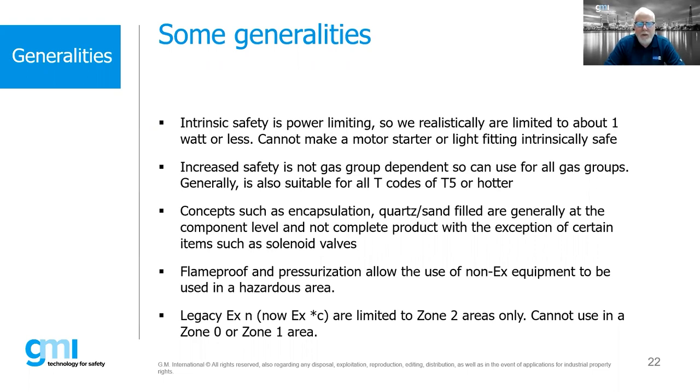Encapsulation and quartz/sand fill are usually done by the manufacturer and are limited to individual components — ballasts, actuators, solenoid valves, fuse holders. One person once asked why we couldn't fill an entire enclosure with encapsulant — the problem is you'd never be able to service or inspect it. It would be basically a disposable panel, albeit a safe one. Flame proof and pressurization allow the use of non-EX equipment in hazardous areas — so if we cannot find an EX widget, these are our options. Also remember: Ex n equipment, now being absorbed into sub-groups like nA, nC, etc., is limited to Zone 2 only.